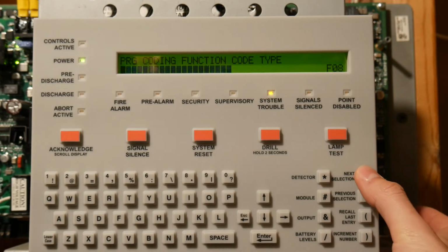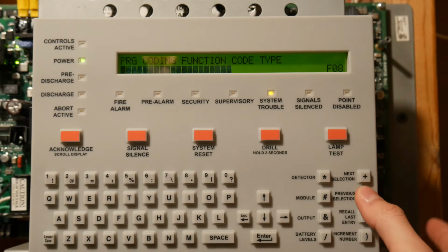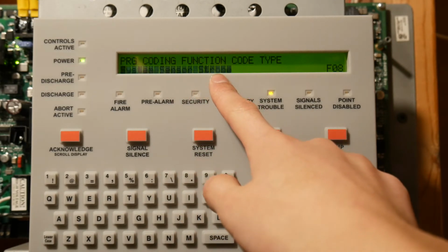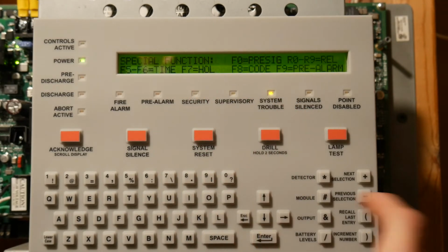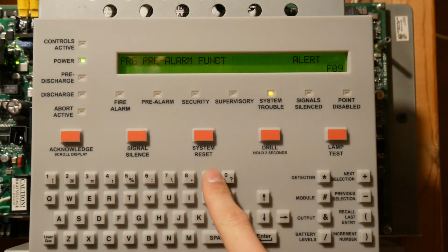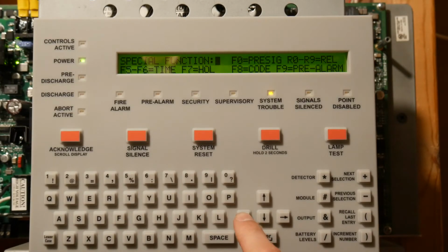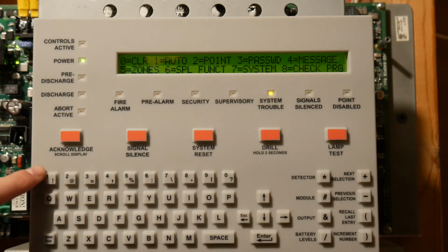So I want it set as system sensor sync. As right here, it says system sensor strobe, so we're going to press enter. And I think F9 is for pre-alarm. Yeah, we're going to keep that the same, so we're going to press enter. Well, escape. And now we're going to program our NAC sync option.